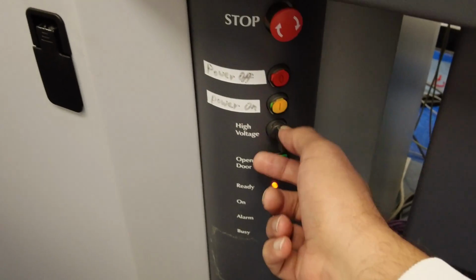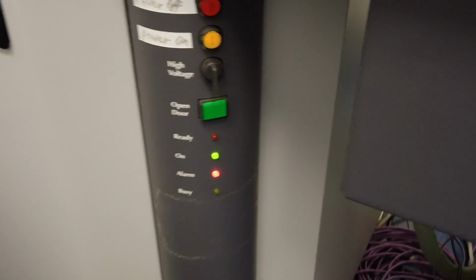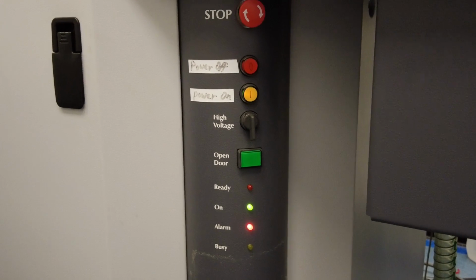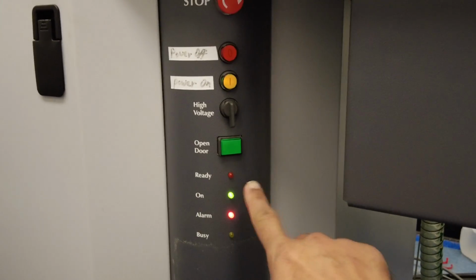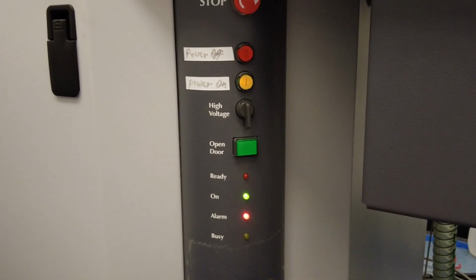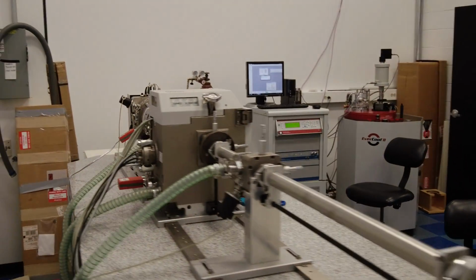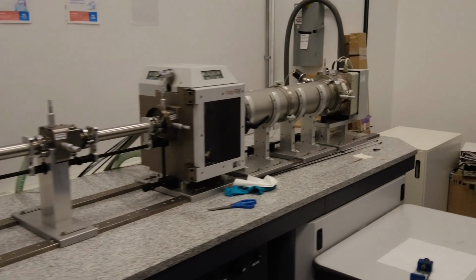And I look here, my X-ray is still on. So I'm just going to turn off the high voltage over here. So once I turn off the high voltage, my ready light has gone, and this alarm light becomes constantly on. I'm not sure what else to do over here. I'm going to have a quick look. Okay, we put back the panel. So there was the cooling unit over here, and we took it out and we filled it with distilled water. So I'm not so sure what else can be done at this point. So any hints or any tips will be helpful. Thank you so much.